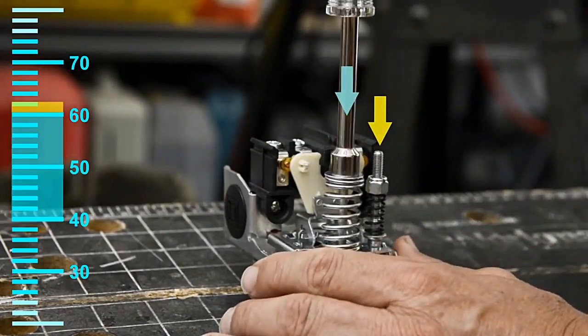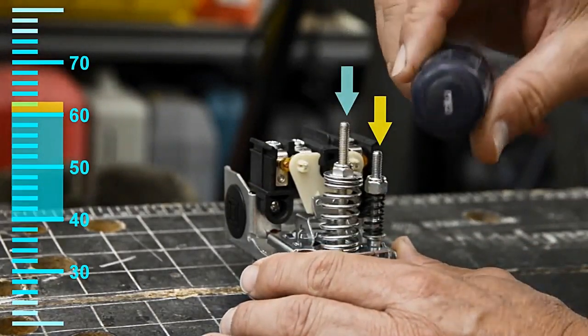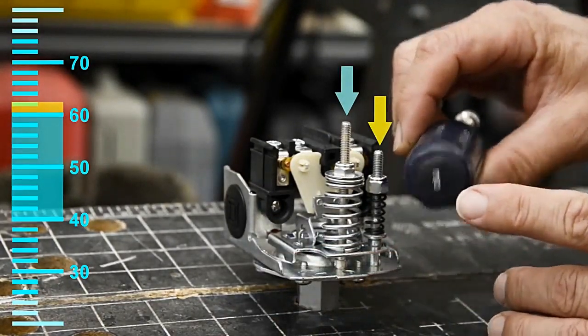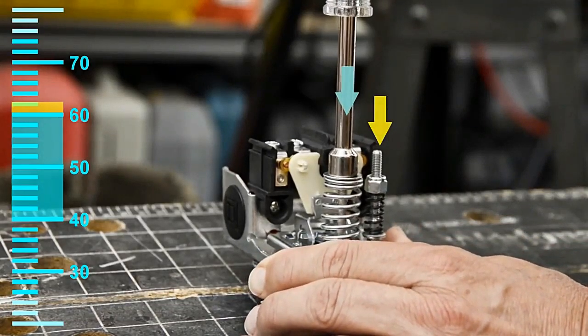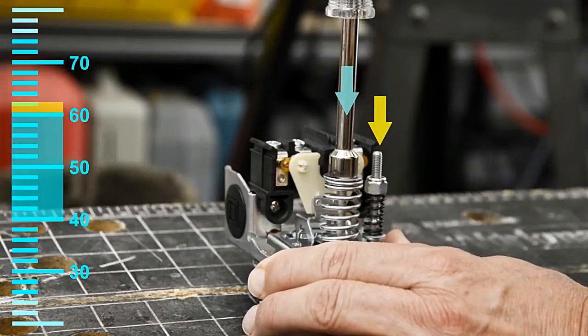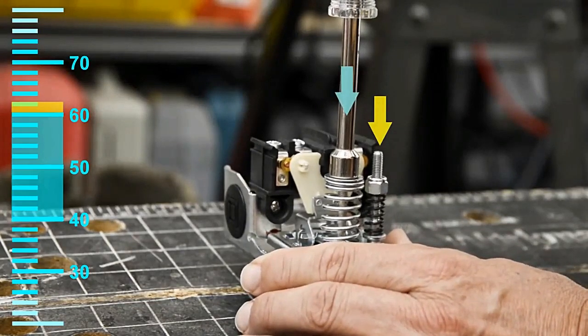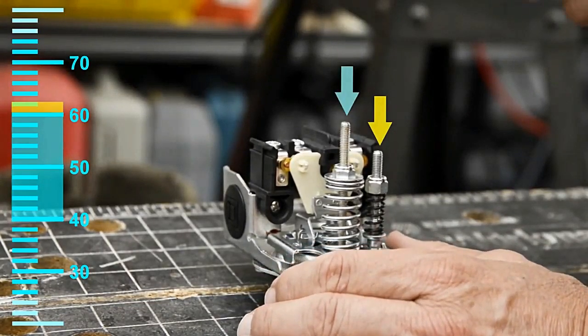So if I was to increase the range I would take a 3/8ths nut driver and tighten it down and that would increase it from 40 upwards. The only way to know for sure is to run a pressure test.